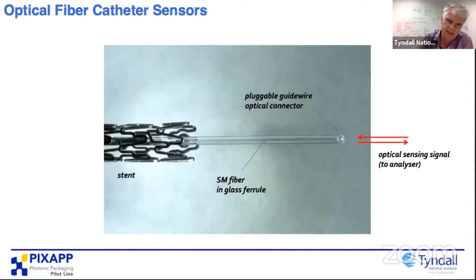What's important in this particular application is that we were able to develop a very nice micro-optical connector. We use micro-optics for data center applications, but this was actually one of our first ventures into using micro lenses on a very small high NA fiber. As I mentioned, the core is around 3 microns. So it enables the surgeon to disconnect the guide wire, put a stent, for example, over that and push it through, and then reconnect it to the analyzer, if you will. So this is a very low loss and pluggable single mode connector. Again, it's using our skills in packaging and micro-optics packaging that normally come out of telecommunications, and utilizing that for medical applications.